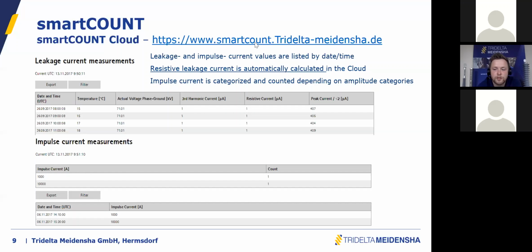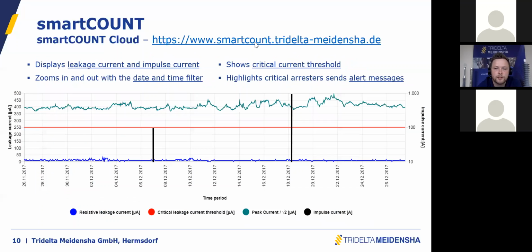And of course, everyone likes diagrams and to look at things visually. That's why we have also included a diagram on the very top of the site, where you will see the different leakage currents in a kind of trend, and you will also see those discharge currents. I will show you now which current is what and what it means. So you have the green line, which is called peak current. That means the peak of the total leakage current.